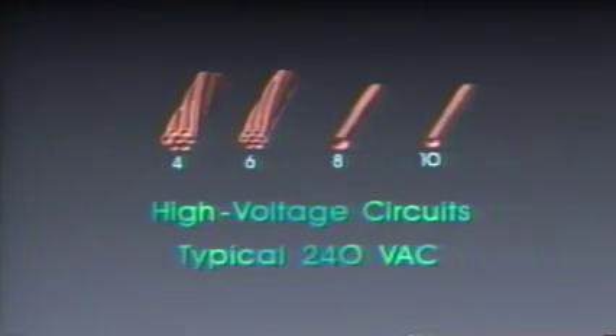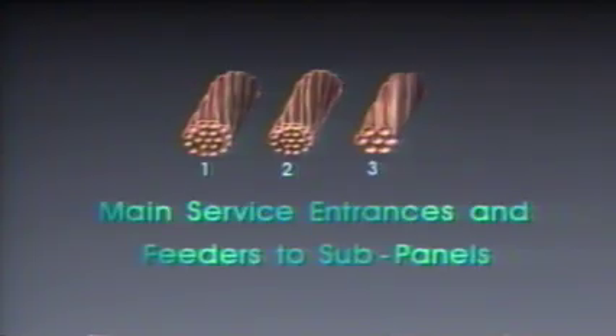Number 10, number 8, number 6, and number 4 wire is used for high voltage circuits, typically 240 volts AC. This wire is usually used for clothes dryers, ovens, ranges, cooktops, water heaters, heat pumps, central air conditioners, and feeders to sub-panels. Number 3, number 2, number 1, and larger wire is for main service entrances and feeders to sub-panels.